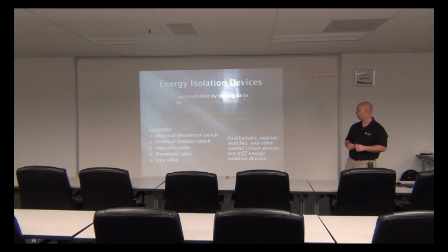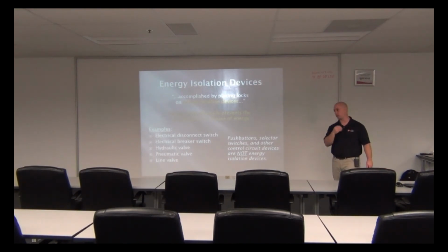Push buttons or selector switches - I don't know if you have anything out here like this that has a little stop button or emergency stop. You pull it out and it stops the equipment, actually shuts off electrical power to it. I don't know if you'd consider it a dead man switch, but it's something like that where you pull it out and it stops it. But you can't use that as a lockout point. It has to actually be a disconnect on a wall that's powering it, or a circuit breaker panel, whatever it is. It could be a main that's powering it, and I don't know if you guys are allowed to do that because it says prohibited on them. So it may have to be a contractor if that happened, because you're not supposed to touch it.